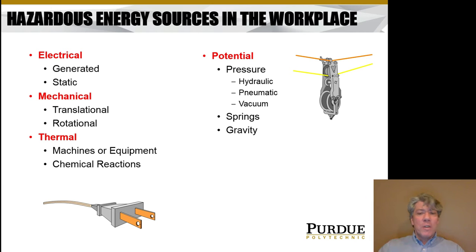Obviously pneumatic systems can contain pressure, and that's a potential source of energy. Even vacuum systems have the potential to do work, so they store energy as well. Springs are an obvious source of stored energy. Potential energy from gravitation acting on a heavy weight is another source. When you have a PLC shut down, you have to think about how it should shut down safely — do you want it to bleed off energy, or hold that energy when it shuts down? It's important to be aware of all these forms of energy and how you prevent any of them from being transmitted to your body.